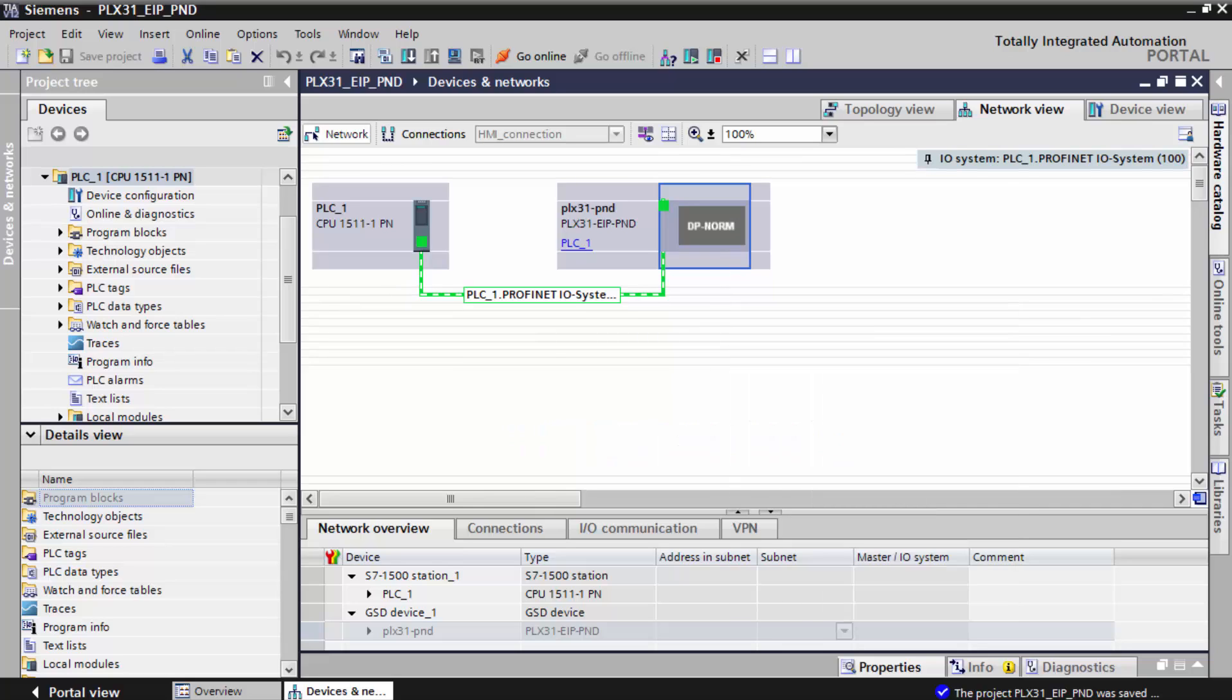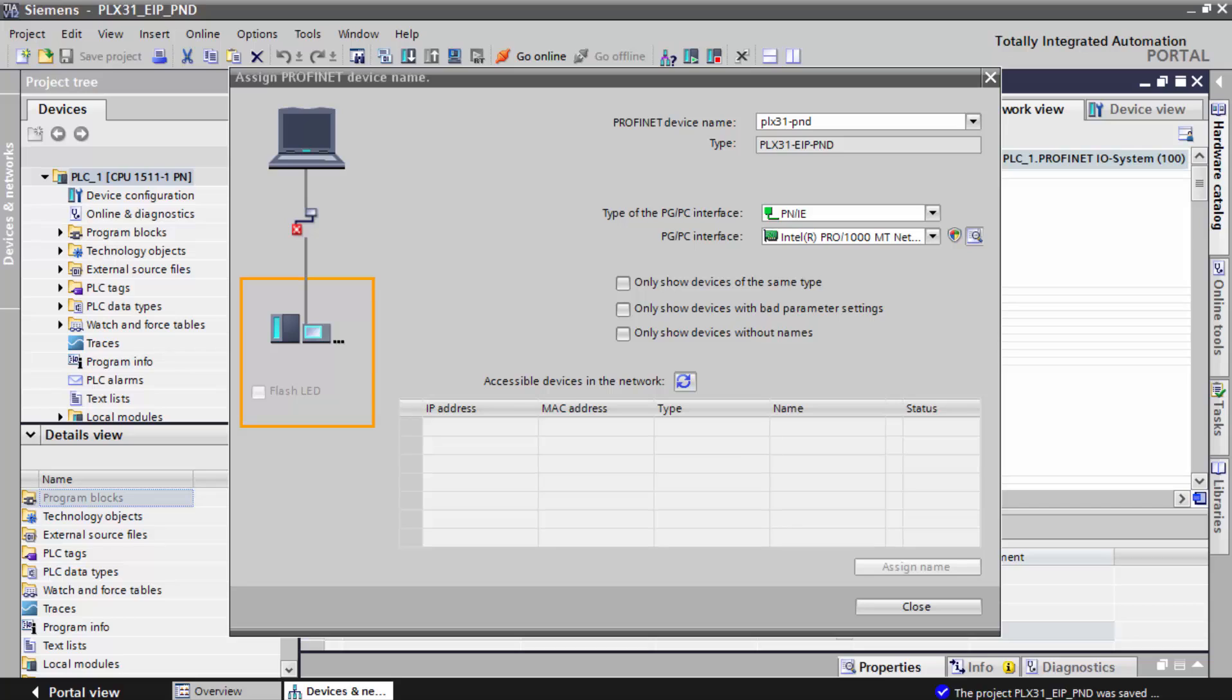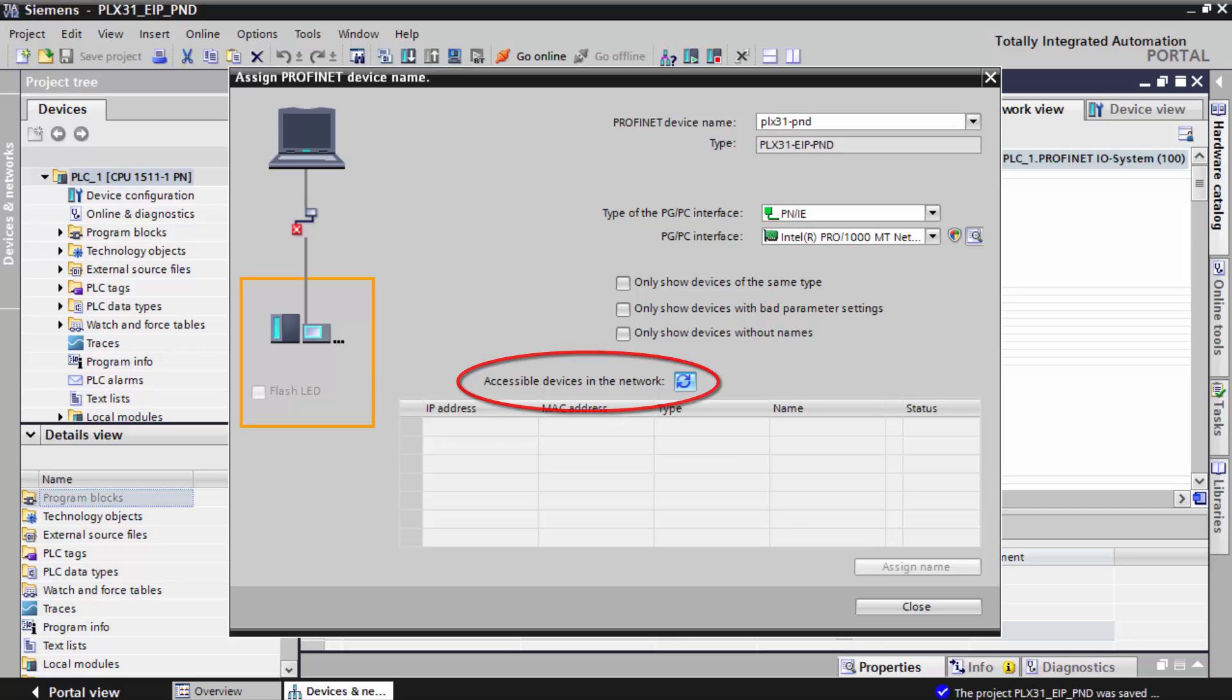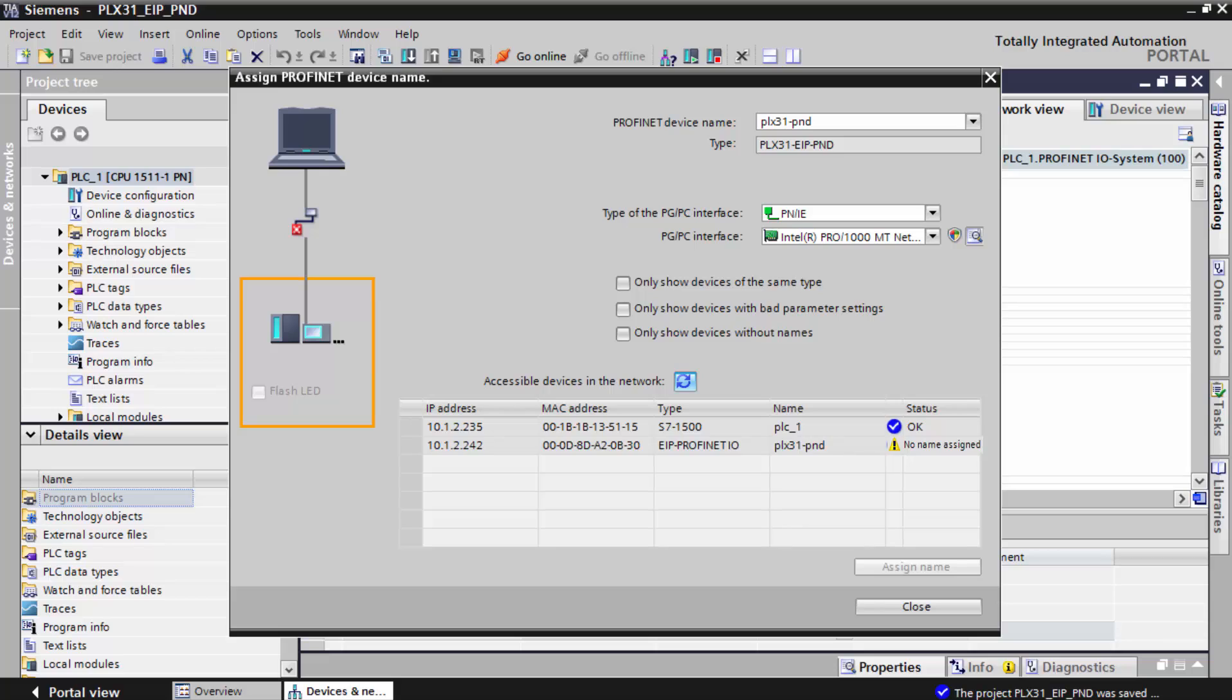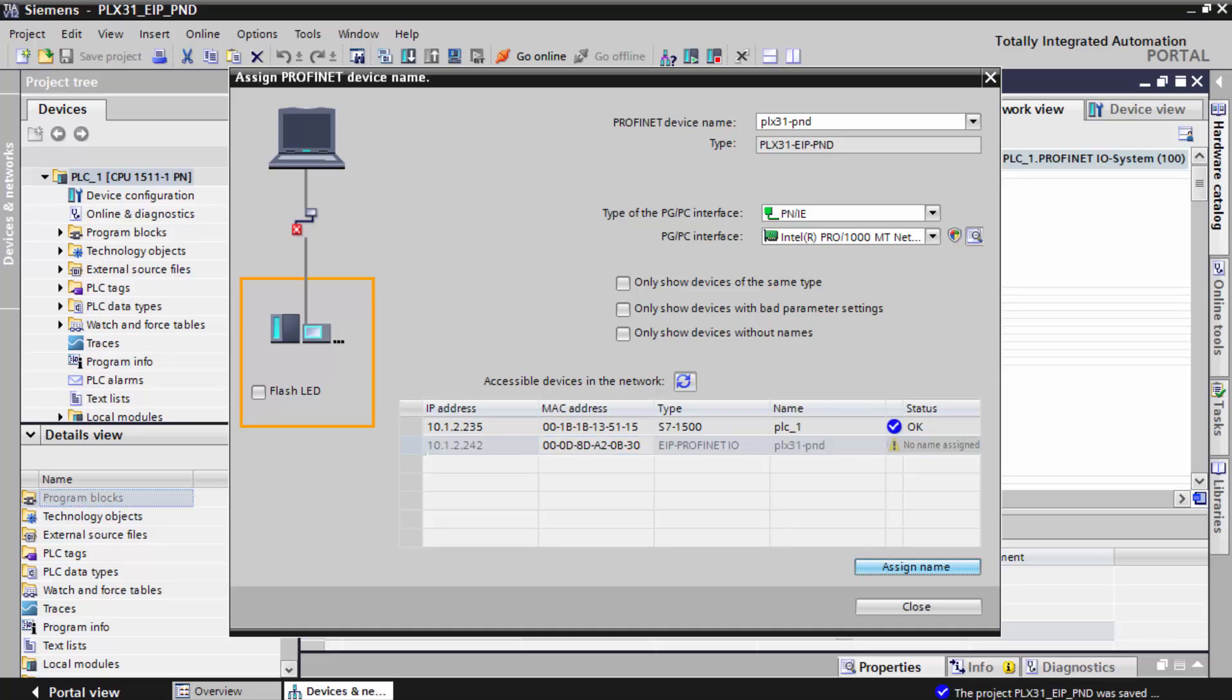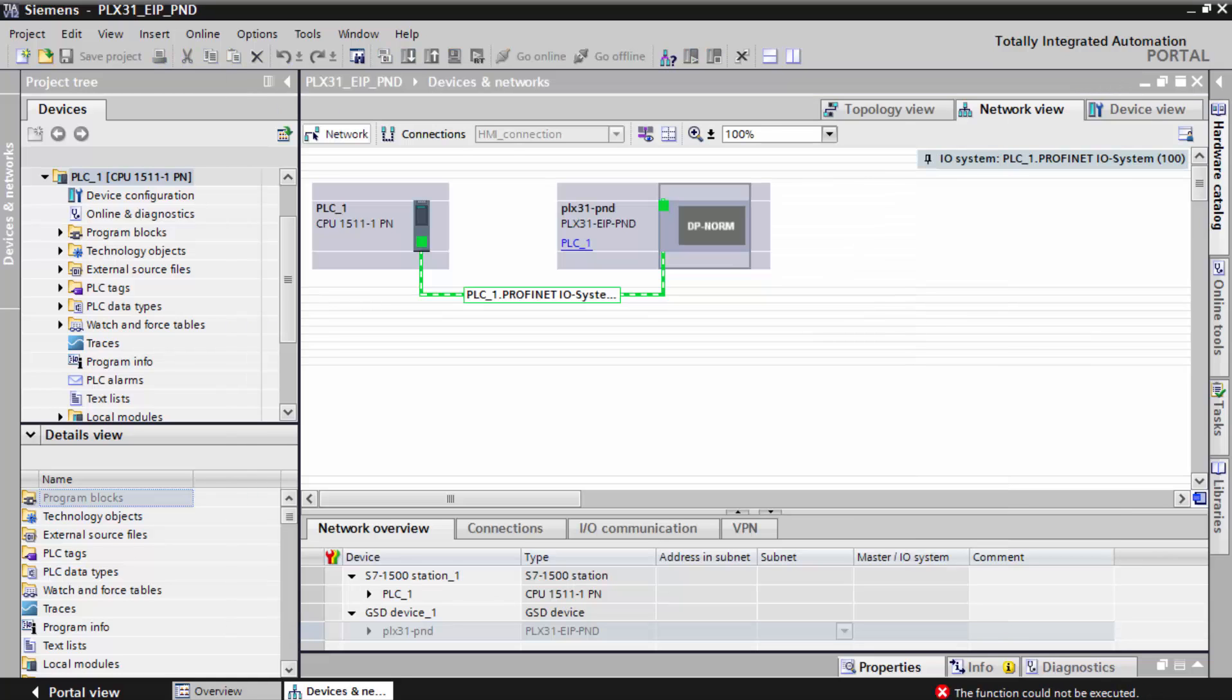Once the window opens, we'll refresh the devices in the network. You should see the PROFINET controller and the PROFINET device. The status will show an exclamation point. Select the gateway in the list and click assign name. The exclamation point will change to check marks indicating that the two pieces are now connected. We'll close this window.